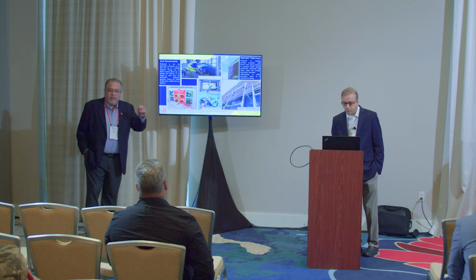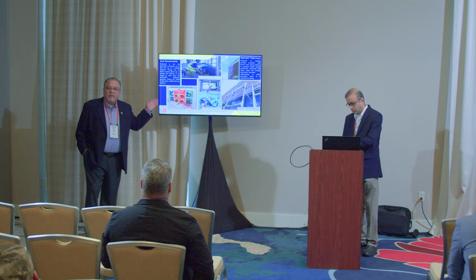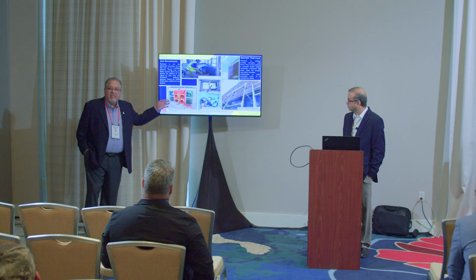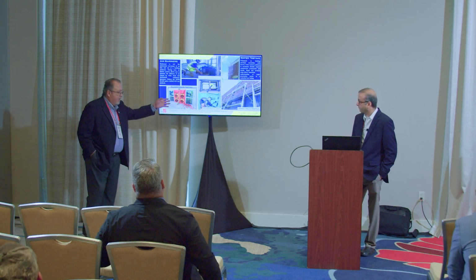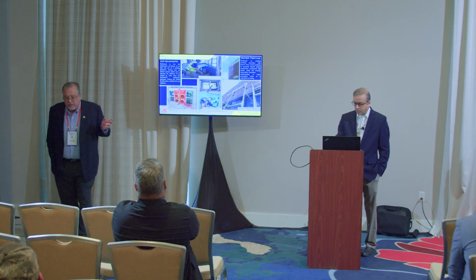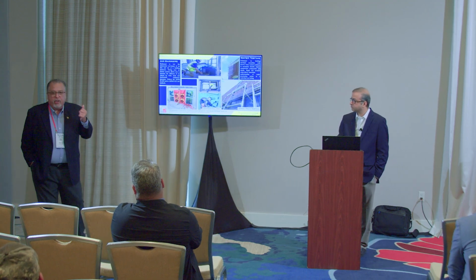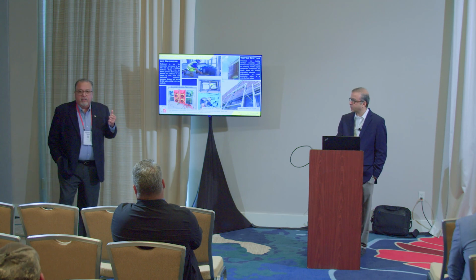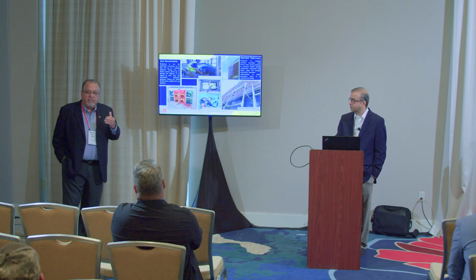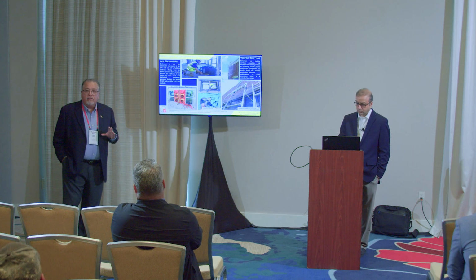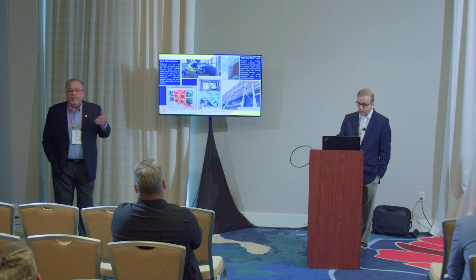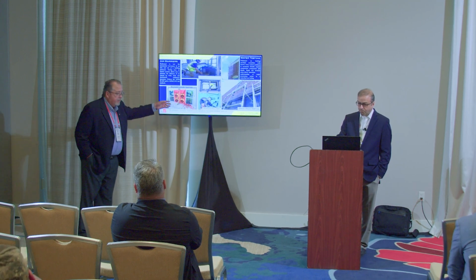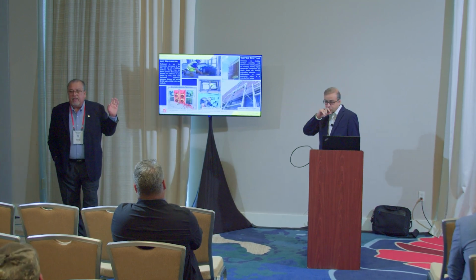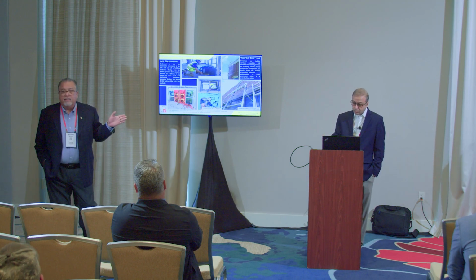This is the one I told you about, the federal courthouse where they went ahead and canceled this test. What's the sense of doing it if you've been failing the whole time? With building pressurization, we depressurize the building and measure the resistance to tell how much it's leaking. Then we have to identify where it's leaking from, so we do infrared testing, making sure there's a 10 degree difference between outside and inside air, which is something we're running into now.